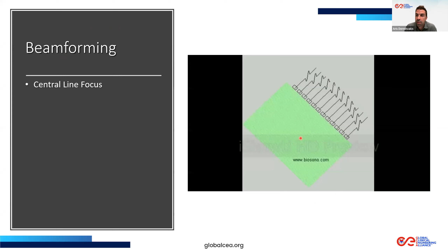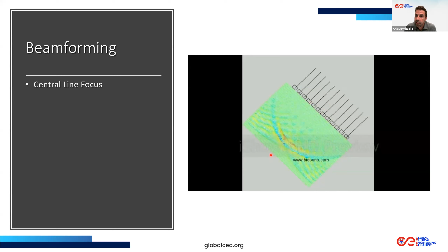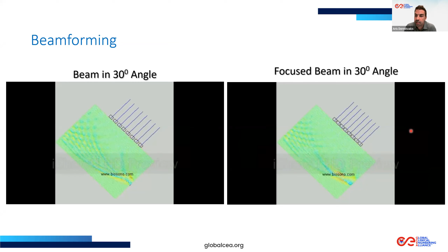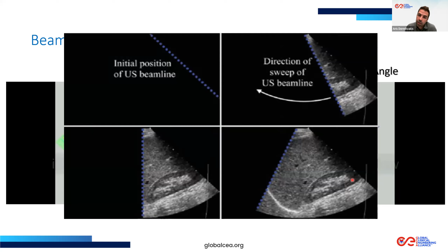And as you can understand better here, we can focus, let's say, in the central line, the acoustic beam, or we can steer it or focus and steer it at the same time. So by applying delays on the time that we excite each piezoelectric crystal in the probe, we are able to steer and focus our beam. And then, thus, we are able to scan a whole area.